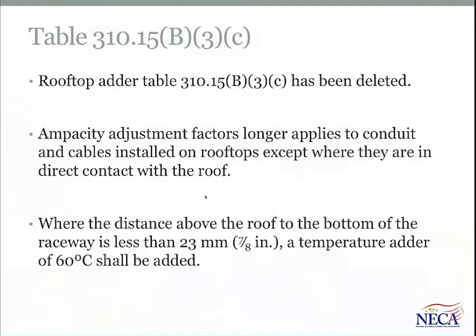Where the clarification and the wording in the code that actually appears is not direct contact, but actually introduces the 7/8 inch, where the distance above the roof to the bottom of the raceway or cable is less than 7/8 of an inch, a temperature adder of 60 degrees C has to be applied. So big change here. It was related to substantiation from large universities that were retained to actually look at historical data and look at some formulas and some methods that NASA uses for gauging temperatures and when to increase things in size and so forth.